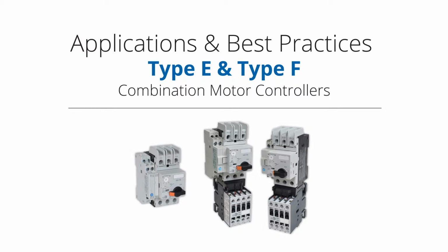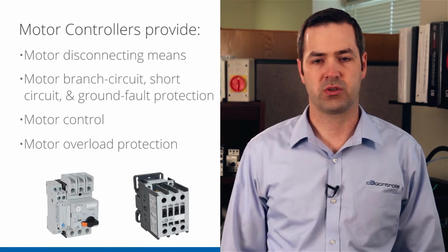The topic of today's application case is Type E and Type F combination motor controllers. A combination Type E and Type F motor controller includes a motor protection circuit breaker and contactor to provide disconnecting means, branch circuit, short circuit, and ground fault protection, motor control, and motor overload protection.